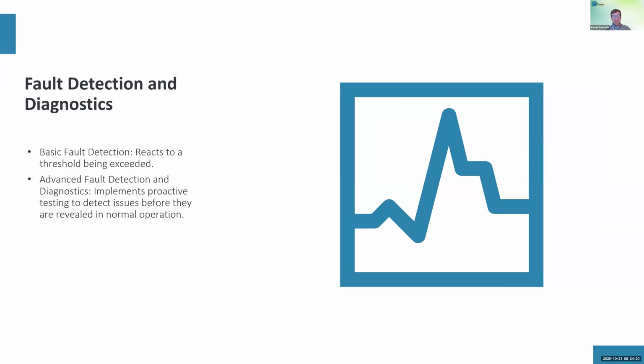Fault detection and diagnostics. This can range from the very simple to the very complex. On the simple end, we have things such as monitoring air filter banks for pressure drop. So you could install an air pressure differential switch across an air filter bank. And when that switch is triggered, it would generate an alarm to indicate that a filter is dirty and needs replaced.